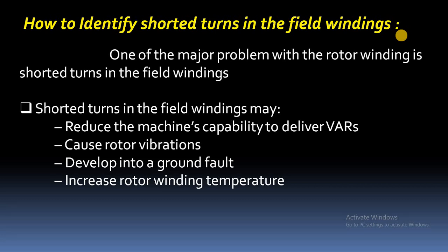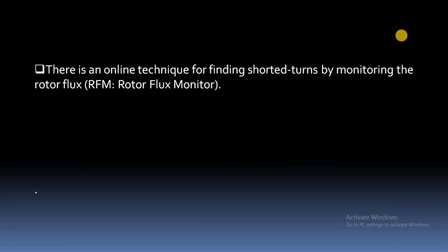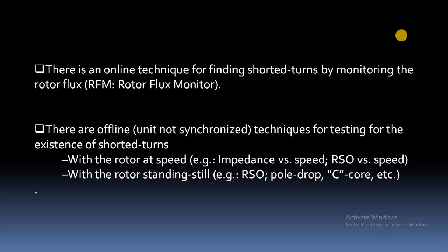Because of these disadvantages, we have to identify the shorted turns. To identify them in the field winding, we broadly have two methods: one is the online technique and another is the offline technique. The online technique is the rotor flux monitoring technique — in real time we monitor the air gap flux, thereby identifying which pole has shorted turns. The offline technique means we are not synchronizing the unit.